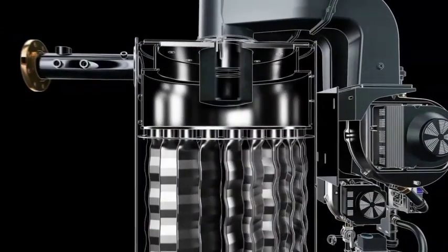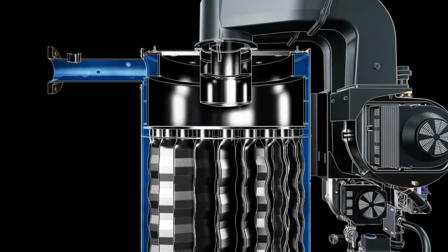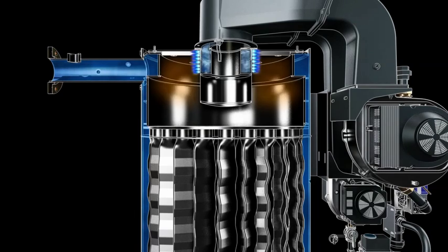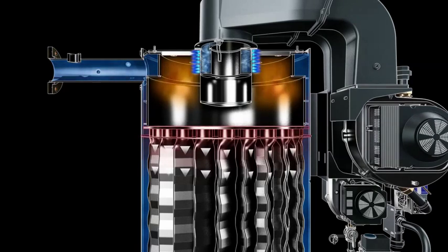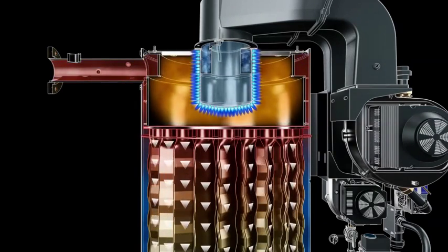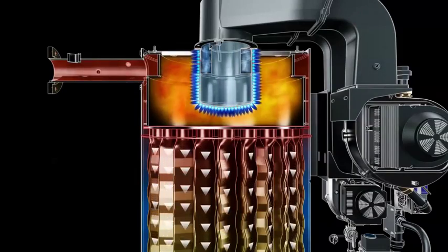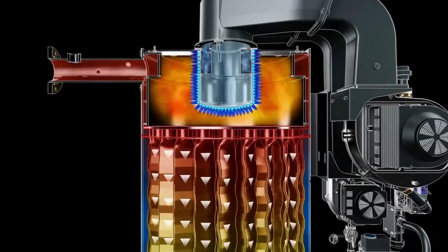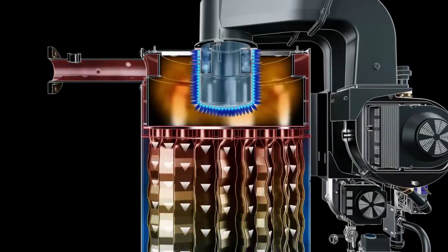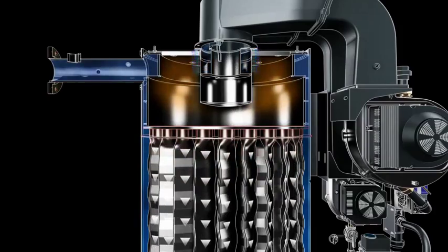In a 2 million BTU Crest, the burner can operate with up to 25 to 1 turn down, firing as low as 80,000 BTUs, modulating with demand up to 2 million BTUs and reversing the sequence for shutdown.